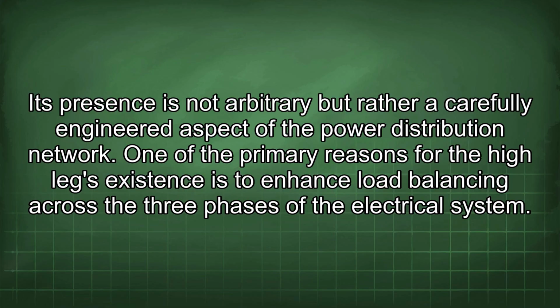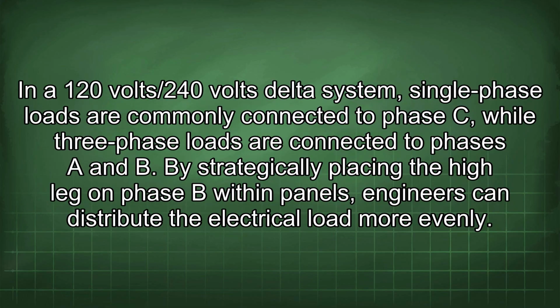One of the primary reasons for the high leg's existence is to enhance load balancing across the three phases of the electrical system. In a 120 volts/240 volts delta system, single-phase loads are commonly connected to phase C, while three-phase loads are connected to phases A and B. By strategically placing the high leg on phase B within panels, engineers can distribute the electrical load more evenly.